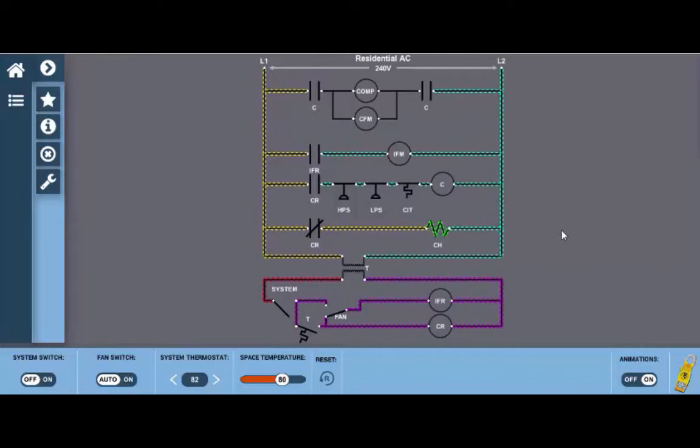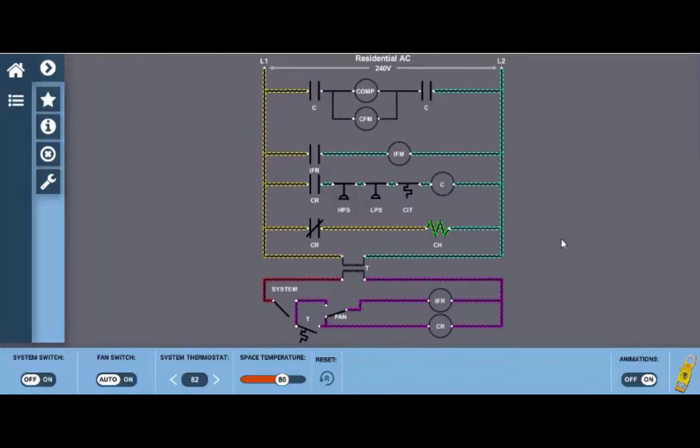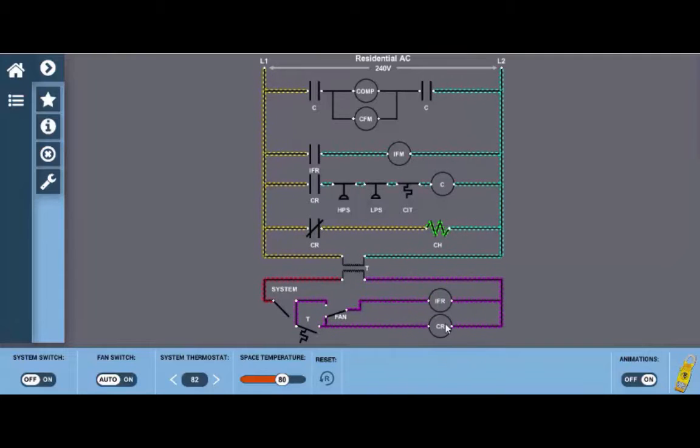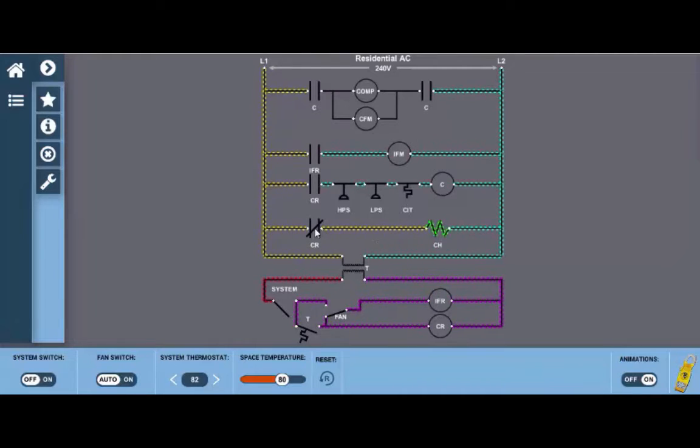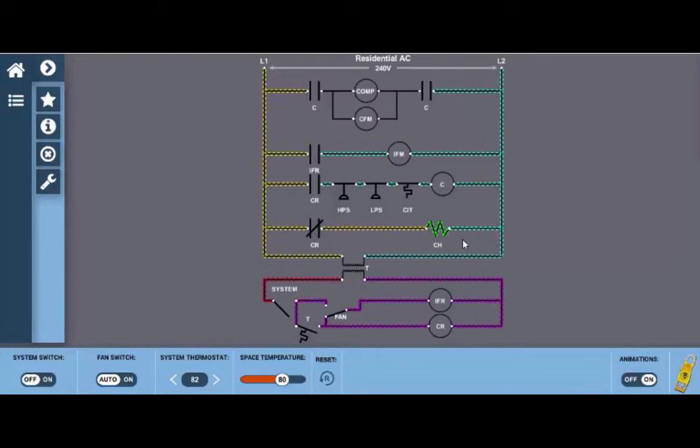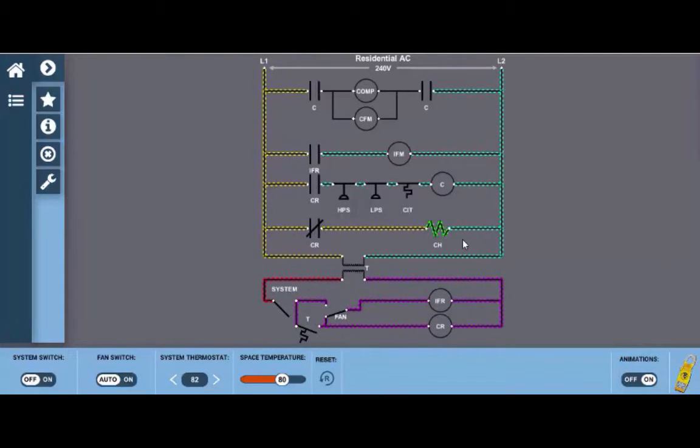Again, the compressor is in a low ambient temperature, has a long off cycle, or there's a large refrigerant charge. Going back to the CR coil here we can see that when it's de-energized the crankcase heater's on, these contacts are closed. We don't need the crankcase heater while the compressor runs because there's plenty of heat there to prevent the refrigerant from condensing.